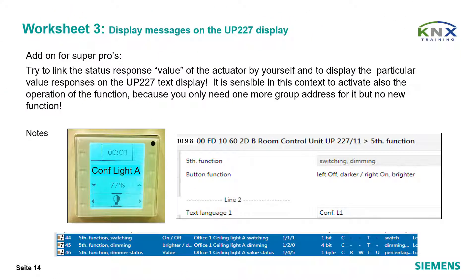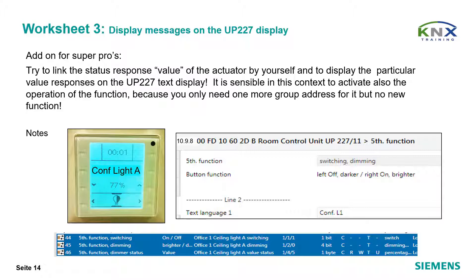Display messages on the UP227 display — add-on for super pros. Try to link the status response value of the actuator by yourself and display the particular value responses on the UP227 text display. It is sensible in this context to activate also the operation of the function, because you only need one more group address but no new function. To get a display indication of the dimming level, the dimming value status of the actuator is required. You prepared it previously in the actuator parameters — now create the new group address and link it accordingly.